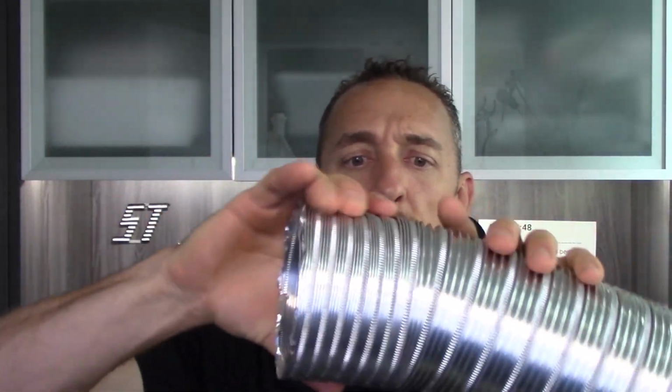There's some other stuff you can find at the store that looks really similar. It's hard to tell the difference, but you stretch this stuff out, and look, just as I was stretching it out, my thumb just smushed into there. I just dented the heck out of this. This stuff is not beefy and strong. However, as a home inspector, it's kind of tough for me to tell the difference between these two. I don't get super whipped up trying to determine, is this actually UL listed or not? Because a lot of the time, I can't even see the UL listing. If I see semi-rigid, corrugated metal, I'm okay with it.